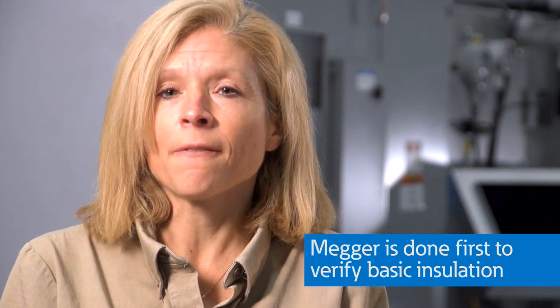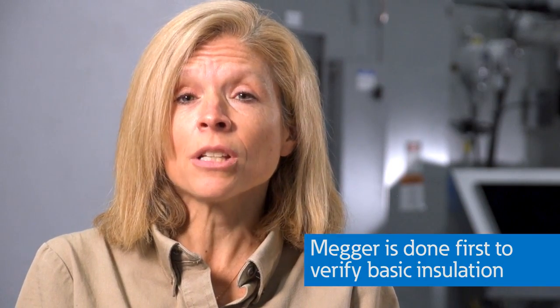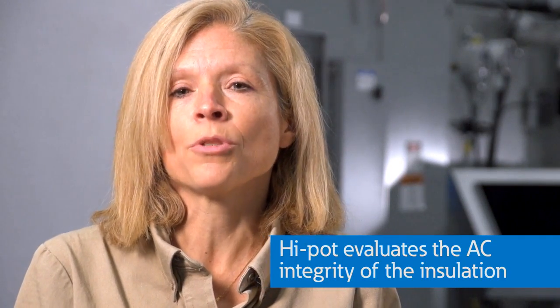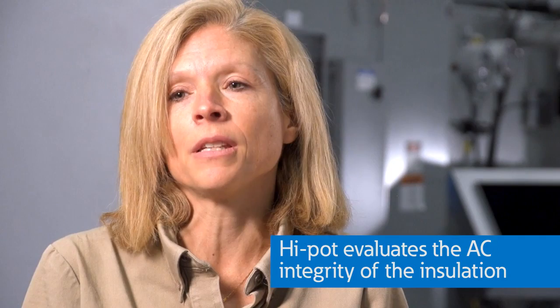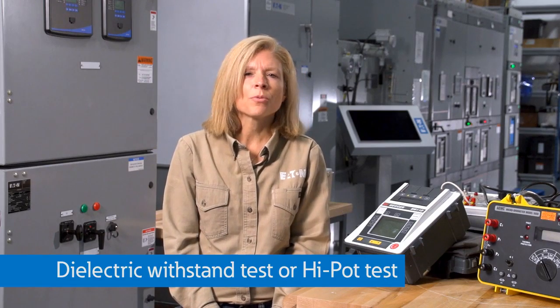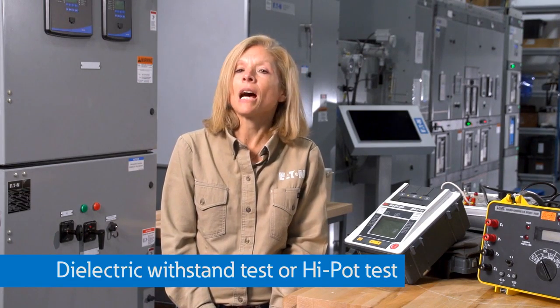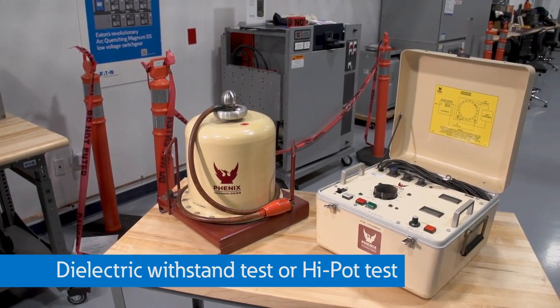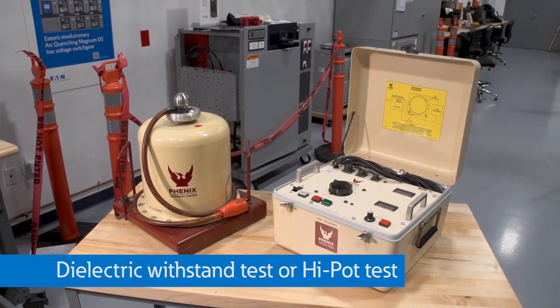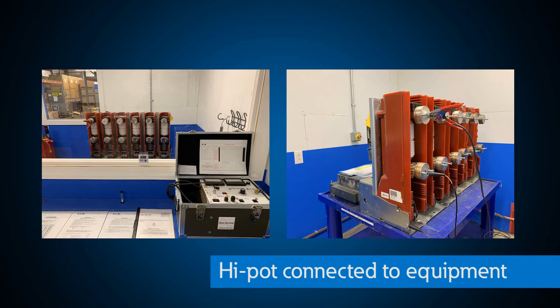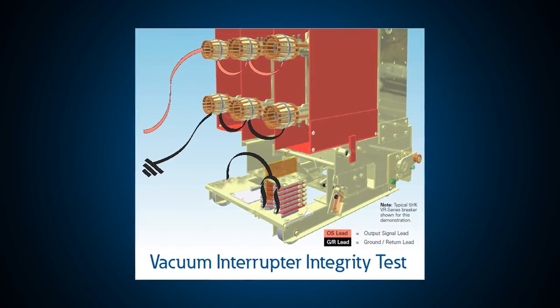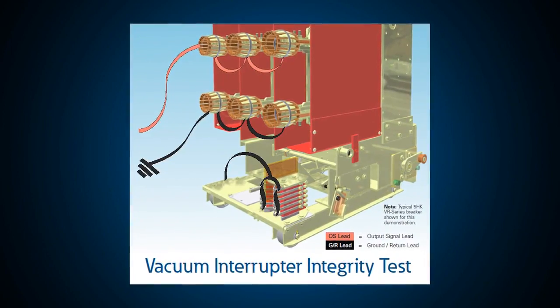Typically, the Megger test is done first to verify basic insulation, and then the hi-pot test is done, which evaluates the AC integrity of the insulation. A dielectric withstand test, also known as a hi-pot test, applies a high AC voltage between an electrical device's current-carrying conductors and its metallic shielding or ground. A hi-pot can also be used to test the vacuum integrity of a vacuum bottle. The leakage current associated with a hi-pot test will typically be milliamps.